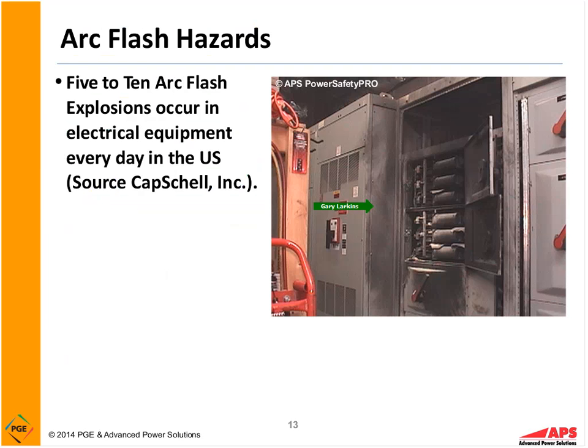In other words, you think 600 amps isn't that much, but yet it is. But you say, well, why didn't the fuse just blow right away? Because the arc occurred on the incoming side to the fuse. Actually the arc went around the edge of the door, it blew a hole through the door, and it blew the door open. So this arc did cause him to get some level of burn. So sometimes even with switching systems or operating systems or racking breakers in and out, we can incur exposure to arc flash hazard even though we're not opening up the gear and working on it directly.